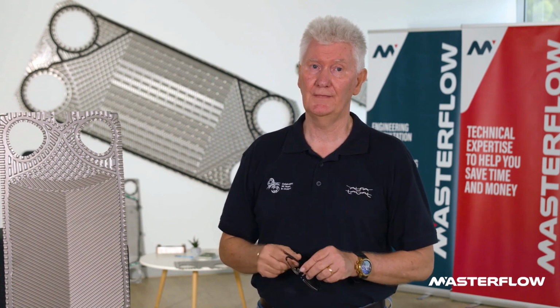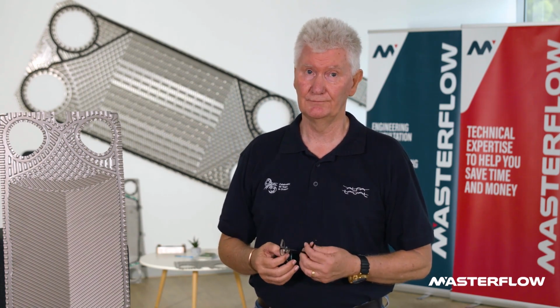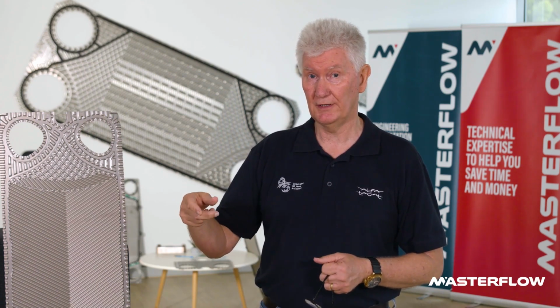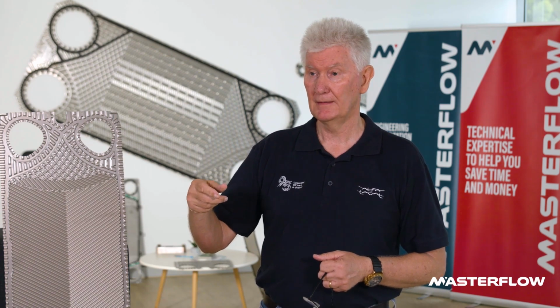The only compromise, well, two compromises, apart from the size of the heat exchanger, is going to be the cost of the pump and the cost of running the pump. Flip that over then, if you're using a cooling tower as your cooling medium, the higher the pressure drop, the less maintenance you will spend on the heat exchanger itself. So you've got a higher pump energy compared against your maintenance cost.